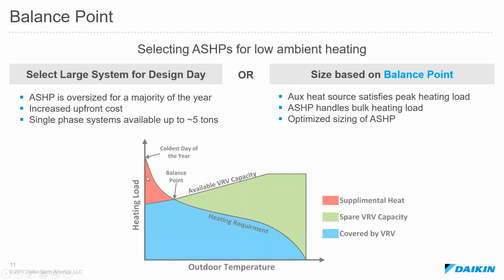On the vertical side, we have the heating load. On the horizontal, we have the outdoor temperature. And what you see here is that capacity curve. It's a simplified curve from what I showed earlier when we were talking about why these systems lose capacity. And then we have our heating load. As it gets colder outside, our heating load is increasing, and our VRV system's capacity is decreasing. Eventually, those lines will cross. Now you can see if we needed a system to meet that design day load, we'd have to increase the size of our system to meet that, or you could use some sort of supplemental source to meet that small portion of the heating load, and have the VRV system meet the bulk of the load.